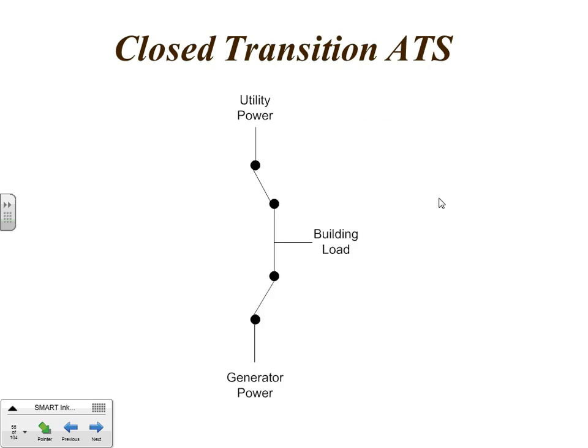This is what it looks like. Again, the utility comes in here, goes through its contactor to the load. And this is showing it at the instant of transfer. Notice both contactors are shown closed here. We actually provide 100 milliseconds of close time, and then the utility contacts come open when you're on generator. Is that clear?